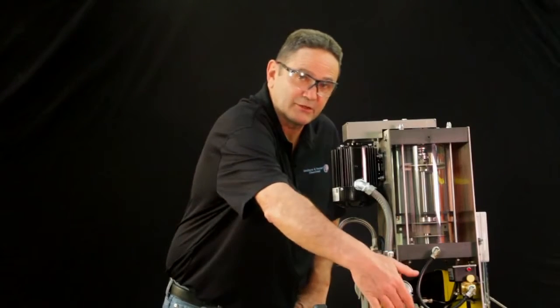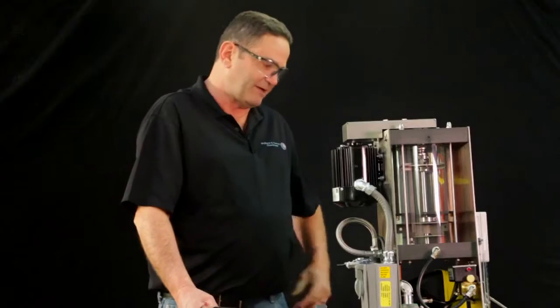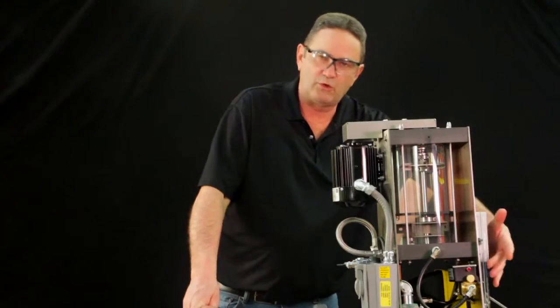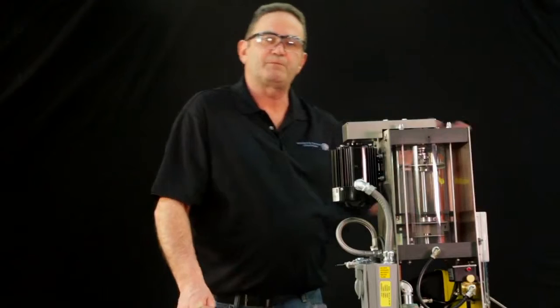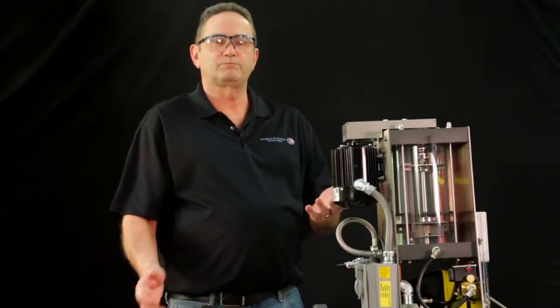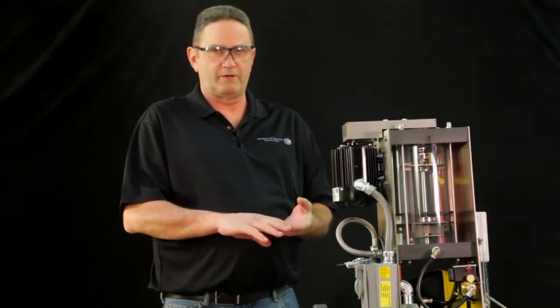If you're using non-potable water, if you have solids in the water, that could actually be contaminating your solenoid, or the coil of your solenoid could be burnt out. At that point, if you suspect the coil of your solenoid is burnt out, I would recommend the assistance of a qualified electrician to check your terminals to ensure that you are getting proper voltage to it. Also, the other common instance is your flow meter located on the front is shut off. Those are your common occurrences for no water flow.